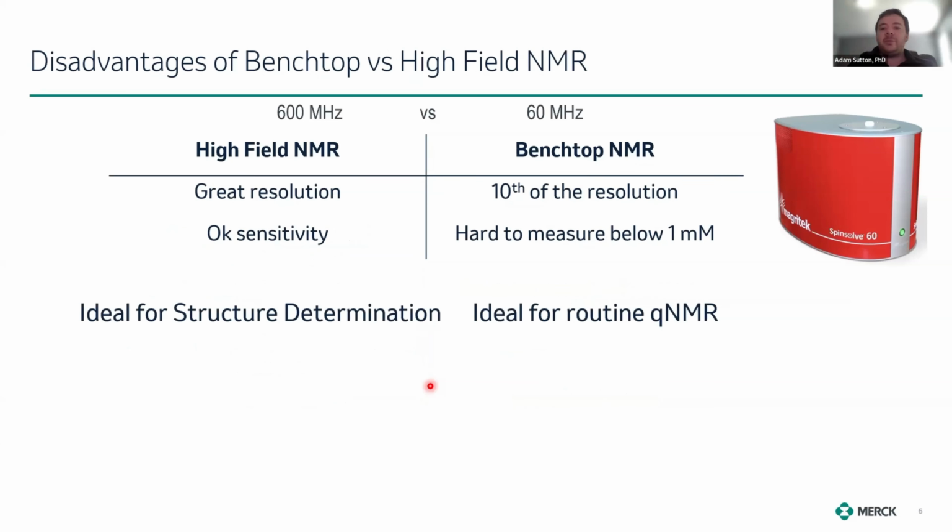Of course, while these convenience and price advantages are really great for benchtop NMR, it does come at a cost. The resolution that you get compared to a high field system is usually about a tenth of the resolution. And sensitivity for NMR in general is quite difficult, so for benchtop systems, the sensitivity is very poor. So we typically only work on measuring things that are above 1 millimolar in concentration.